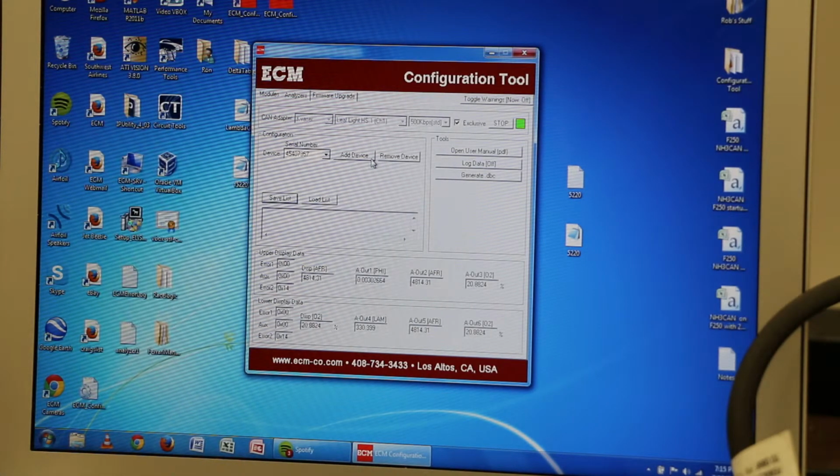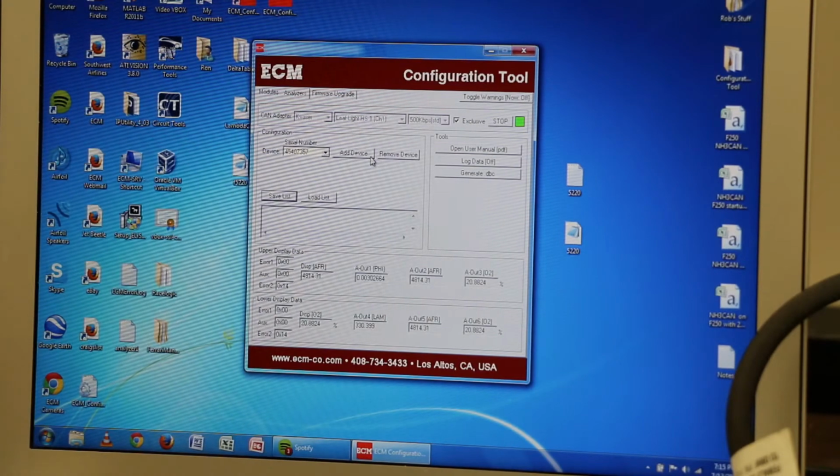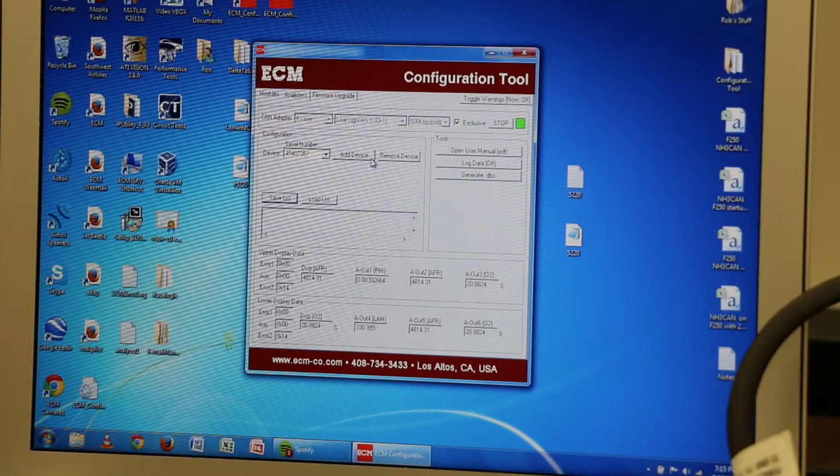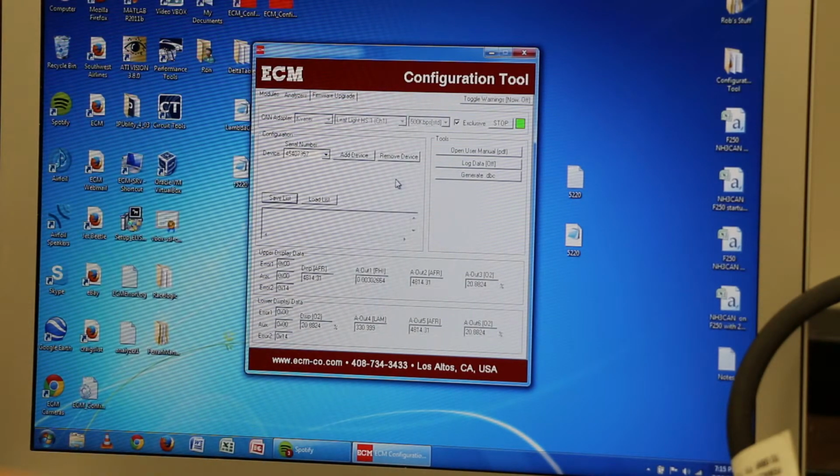Go to the CAN setting. Work your way through the addresses, the 5 addresses. You must make them different for the different analyzers. And then when you get to the CAN, you press it, you get the rolling wheels, and that will be sent up. That file you can send separately. If you don't, it's going to be appended to whatever you previously did. In this case, we just have the one analyzer, so our data has been uploaded.